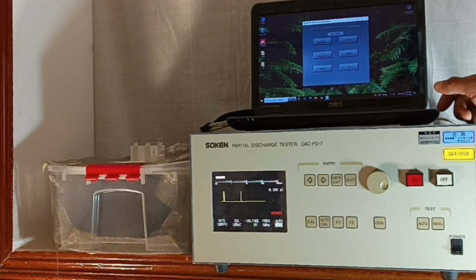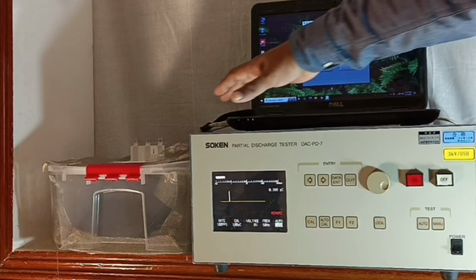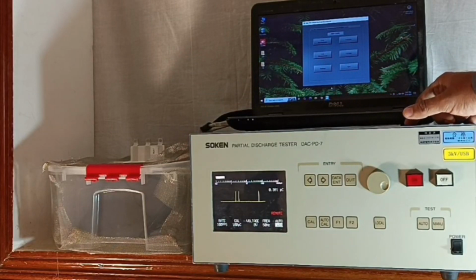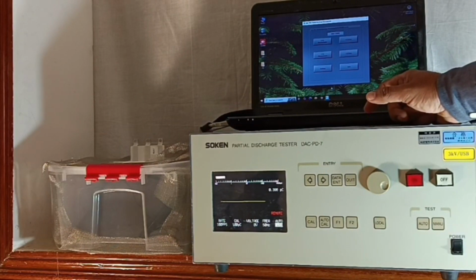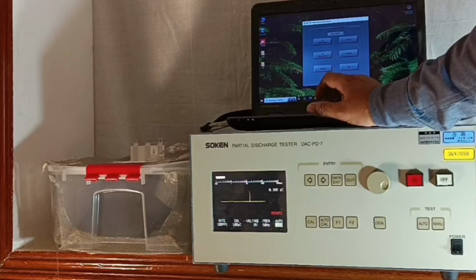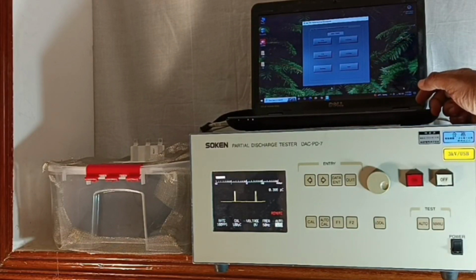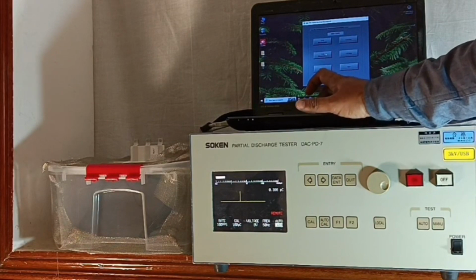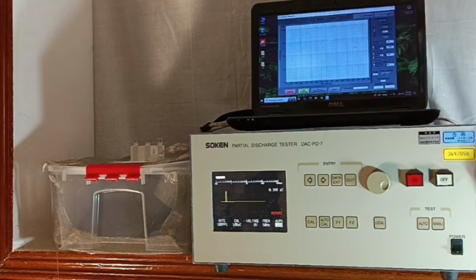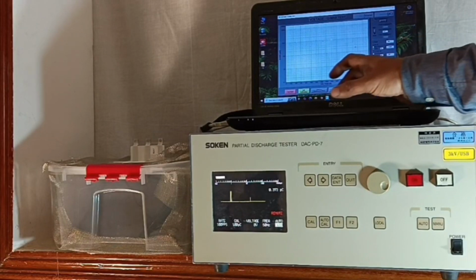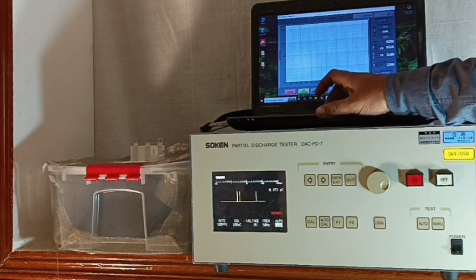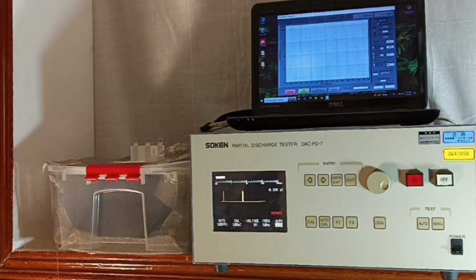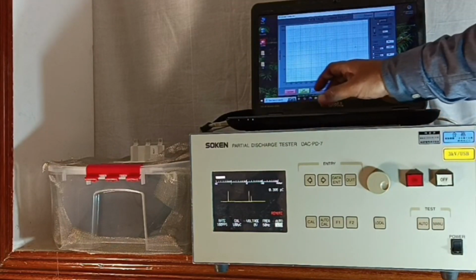Now, at this location, we have made a small Faraday cage, which we could achieve 0.378 or even less PC as the background noise. To make it very short, we have this setup in an automatic way. We will have a measurement with the setup in an automatic way. You have the PD generated from the twisted pair built in inside.